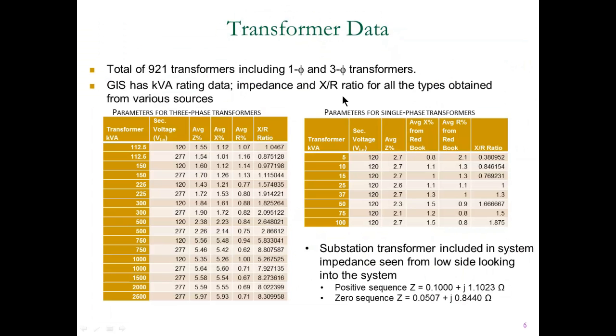Regarding the transformers, there are several single-phase and three-phase transformers, and for each of the transformers, the corresponding electrical parameters, mainly the impedance, the X and R, and the X over R ratio for both three-phase and single-phase transformers were obtained. As you can see, for the single-phase transformers with very low kVA, the X over R ratio is very small, typical of low power distribution transformers. The main substation transformer was also modeled using its positive and zero sequence impedance, looking from the low voltage side into the sub-transmission system.